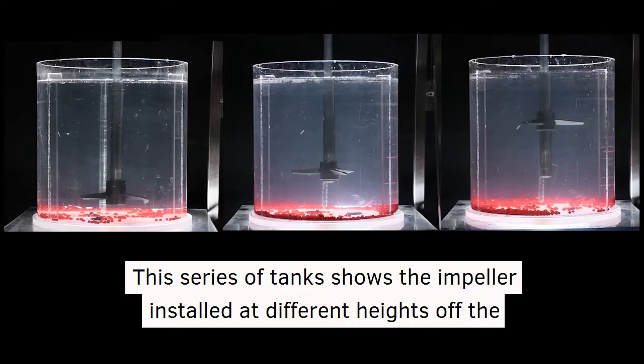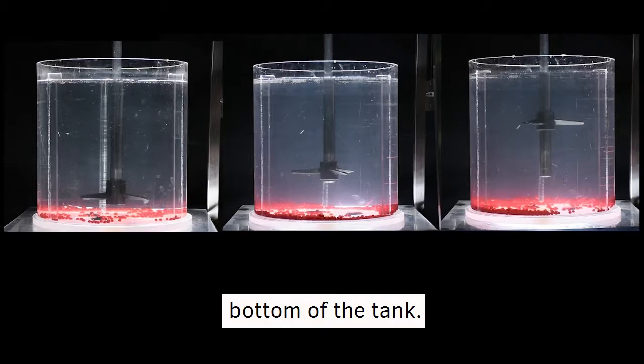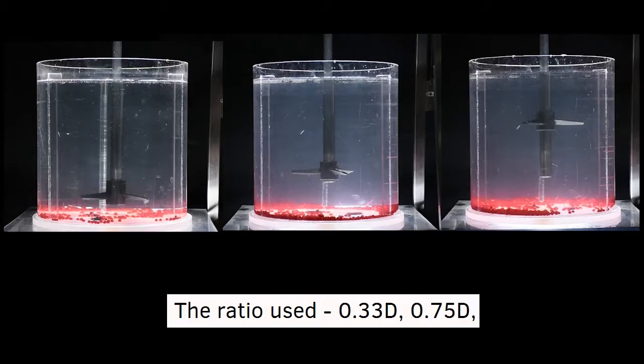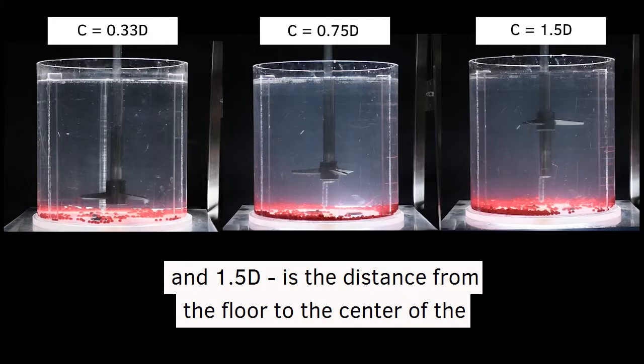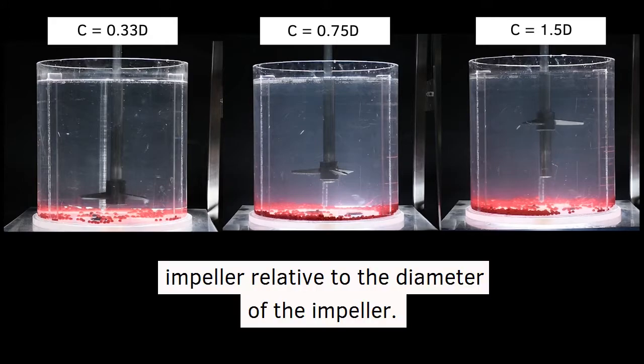This series of tanks shows the impeller installed at different heights from the bottom of the tank. The ratios used are 0.33D, 0.75D, and 1.5D, where C is the distance from the floor to the center of the impeller relative to the diameter of the impeller.